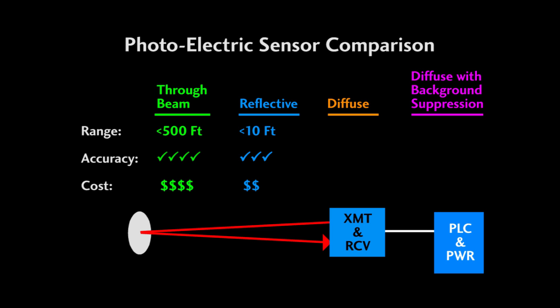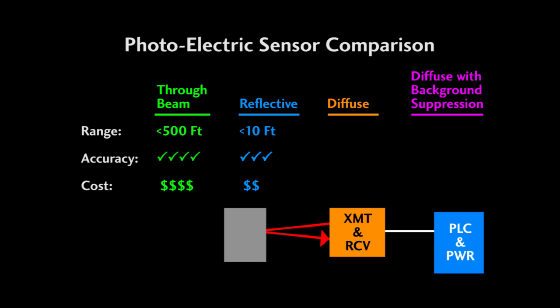While the through beam and reflective sensors are looking for an interruption of the beam, diffuse photoelectric sensors actually look for the object to reflect the beam. This is great for those situations where you don't have access to the far side of the object. The downside of this is it is heavily dependent on the reflectivity of the object passing by, has a shorter detection distance, and is less reliable.